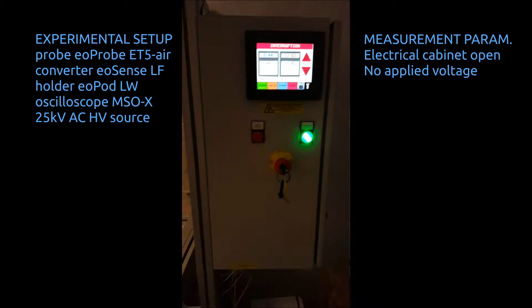In order to illustrate the breakthrough in ultra-high spatial resolution partial discharge detection, we've used a classical experimental bench with a high voltage source swinging up to 25 kilovolts and a high voltage cable. We've cut this high voltage cable and put at its end an electro-optic probe to sense the vertical E-field component.